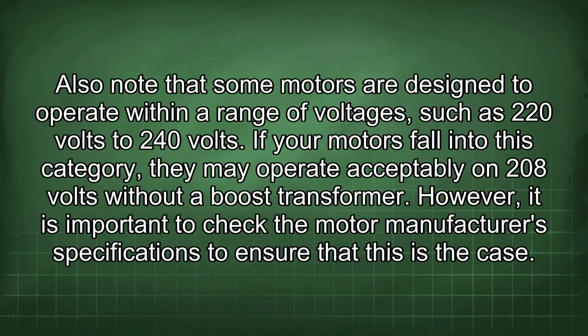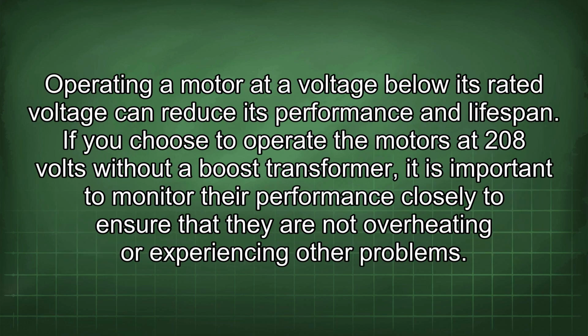Also note that some motors are designed to operate within a range of voltages, such as 220 volts to 240 volts. If your motors fall into this category, they may operate acceptably on 208 volts without a boost transformer. However, it is important to check the motor manufacturer's specifications to ensure that this is the case. Operating a motor at a voltage below its rated voltage can reduce its performance and lifespan.